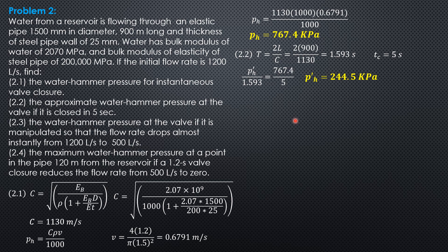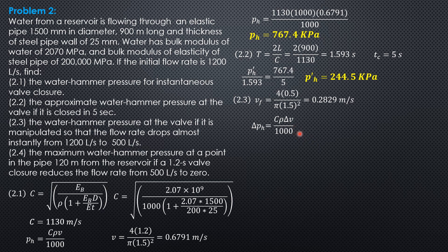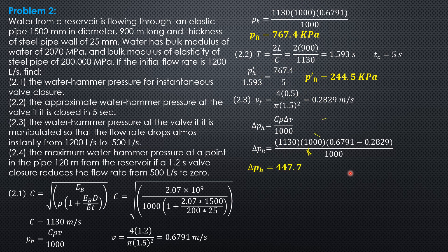For Part C, the water hammer pressure at the valve when flow drops almost instantly from 1,200 to 500 liters per second. Delta pH = C × ρ × ΔV / 1,000. The final velocity V_final = 4 × 0.5 / (π × 1.5²) = 0.2829 m/s. So delta pH = 1,130 × 1,000 × (0.6791 − 0.2829) / 1,000 = 447.7 kilopascals.